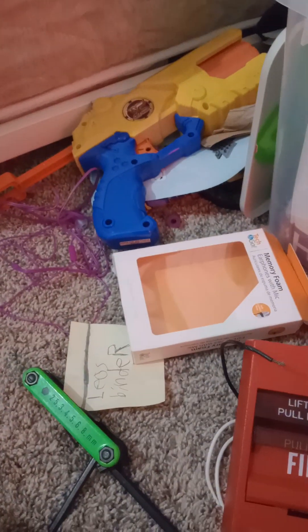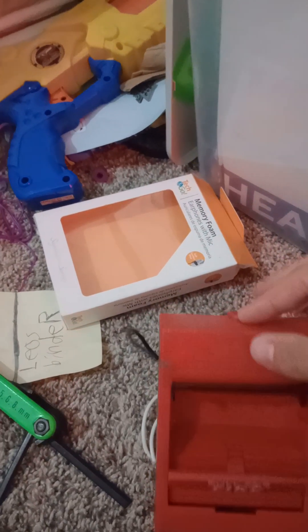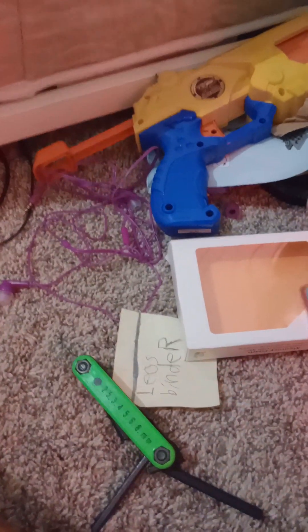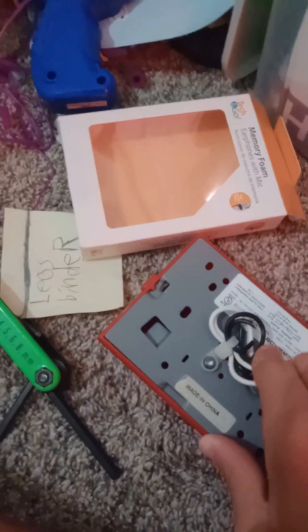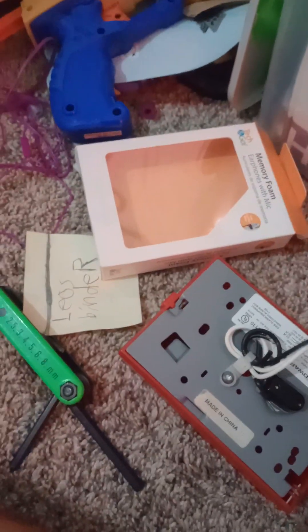We're missing one more — the Edwards pull station. I activated it and it's going to reset. One pull station is destroyed — I'm going to fix the wire. One wire is cut and another wire is missing.